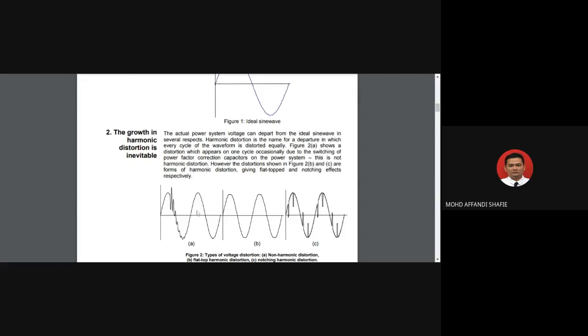What does distorted equally mean? It means that every cycle of the waveform is distorted. If we refer to the figure here, for each cycle we can see the harmonic content in the positive cycle and the negative cycle. Figure 2A shows a distortion which appears on one cycle, due to the switching of a power factor correction capacitor on the power system.